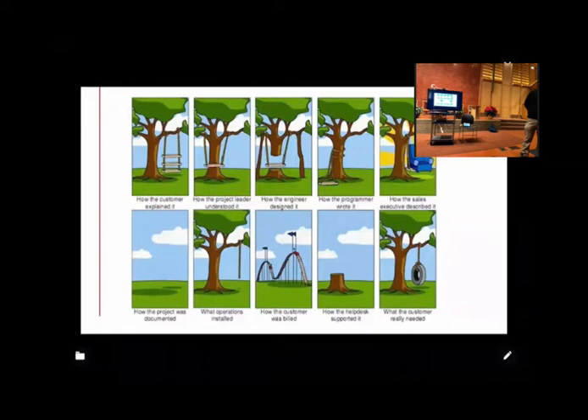Other times we had added electronic controls to motors for the classrooms. That's because the volume was producing so much noise, so that was some noise issue. We turned it down. Yeah, so there were steps like that. Switching lighting over to LED as we could. All of these things contributed to dropping our electric bill.